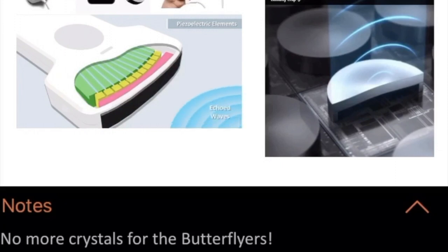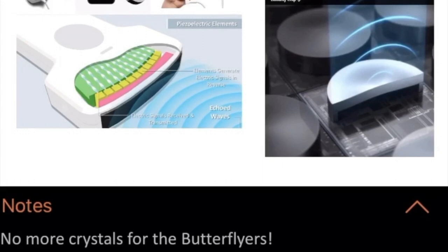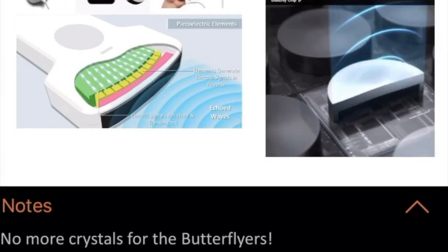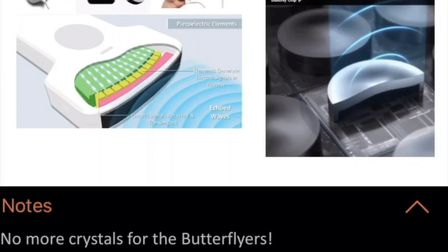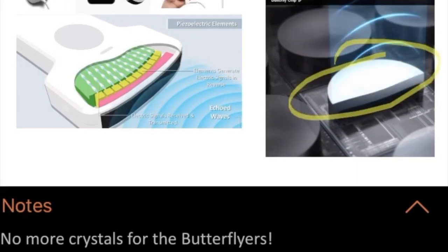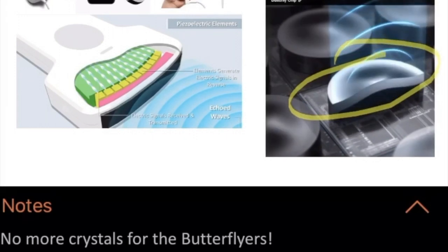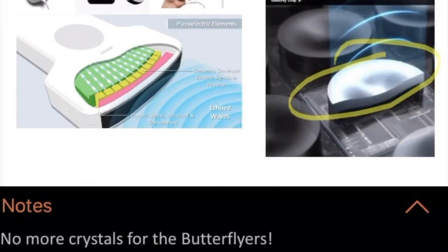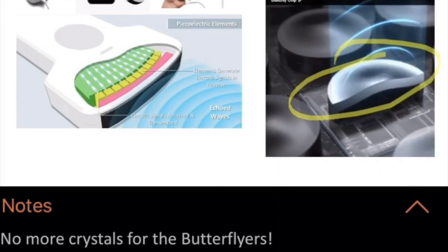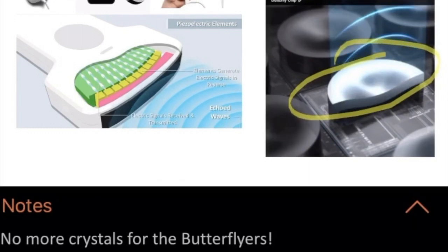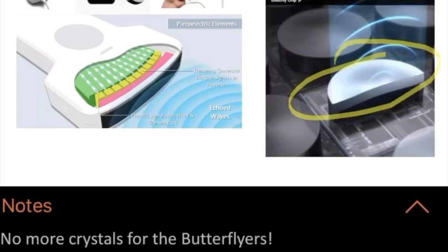So most of the machines actually use piezoelectric elements or piezoelectric crystals, and these are the basic elements in these devices, most of the handheld devices that we have, like the V-scan, the Clarius, and the Lumify. Now the Butterfly uses a totally different mechanism. The device doesn't have the piezoelectric elements or crystals. It actually has a chip, and this is probably one of the reasons why the device is cheaper than the other devices. Also, per the manufacturer, it's probably stronger, meaning if the probe fell to the ground, it's more likely not to be damaged compared to the other devices.